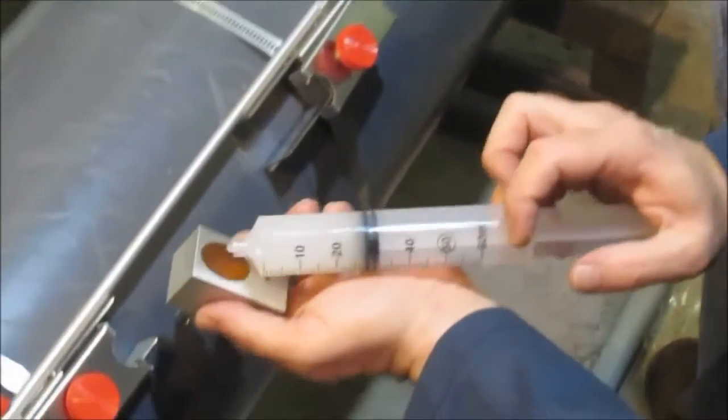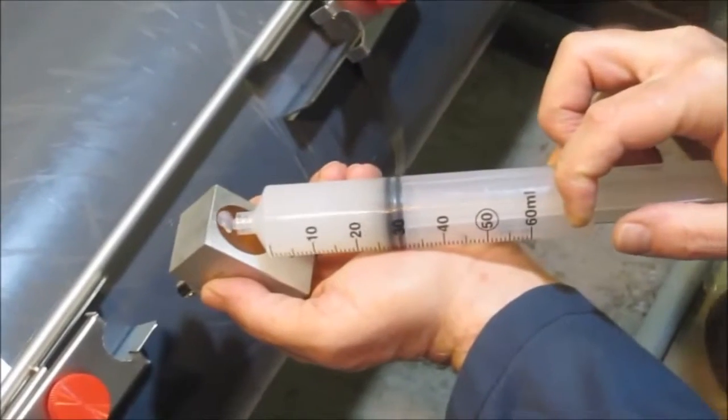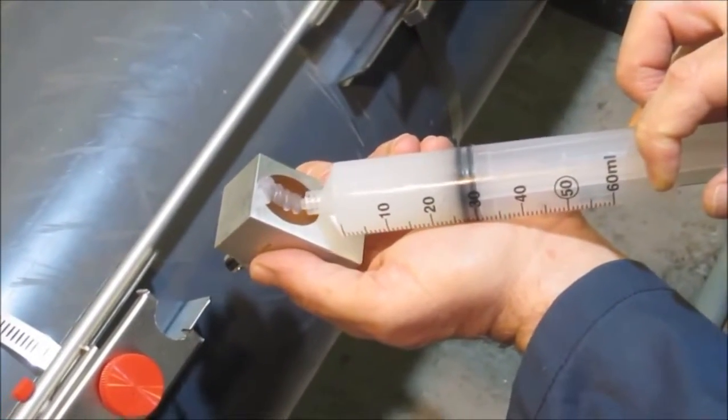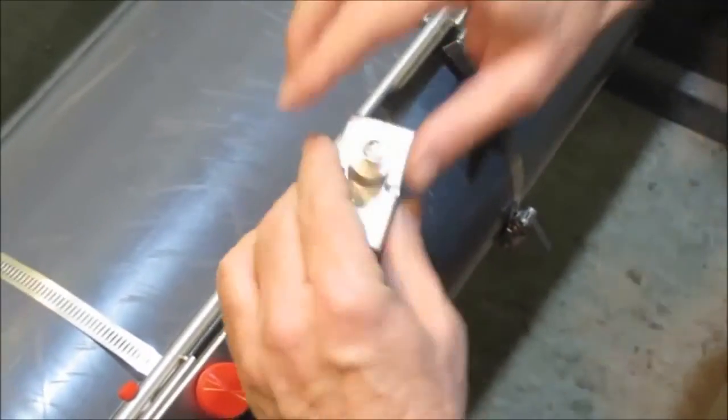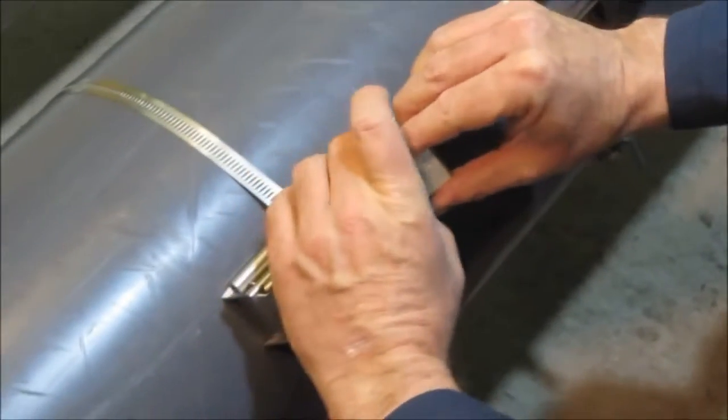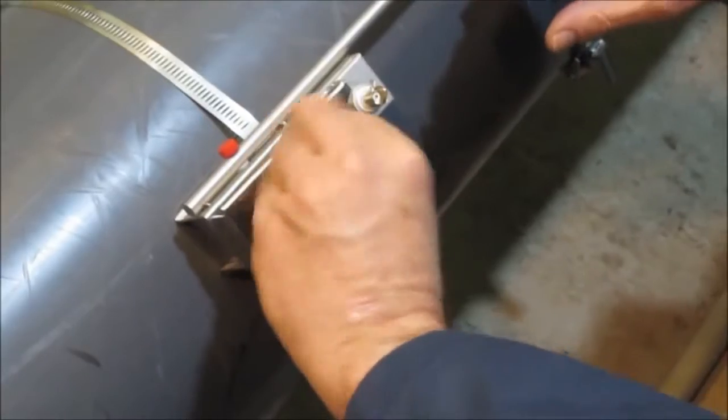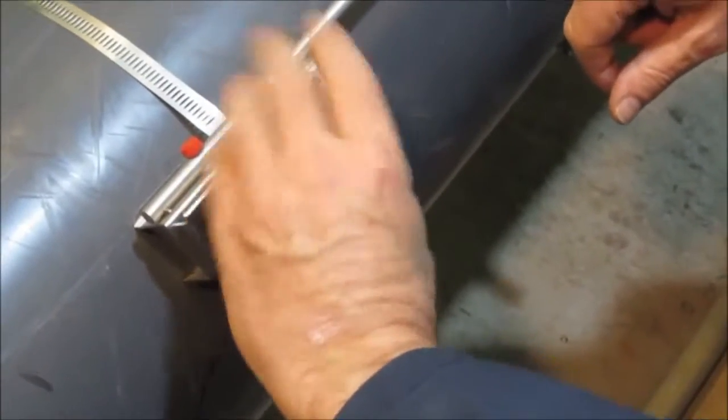Coupling compound is applied to the face of each transducer to help conduct sound efficiently into the pipe. Then we insert the transducer into the mounting bracket and secure in place.